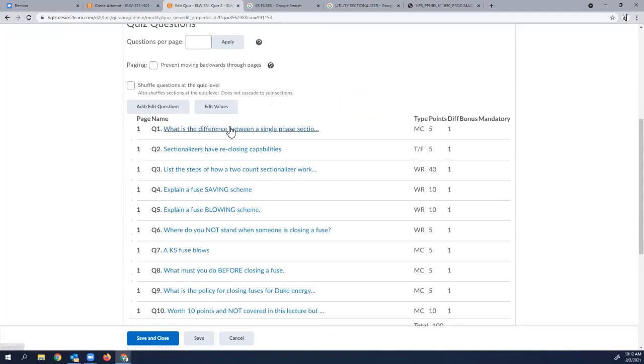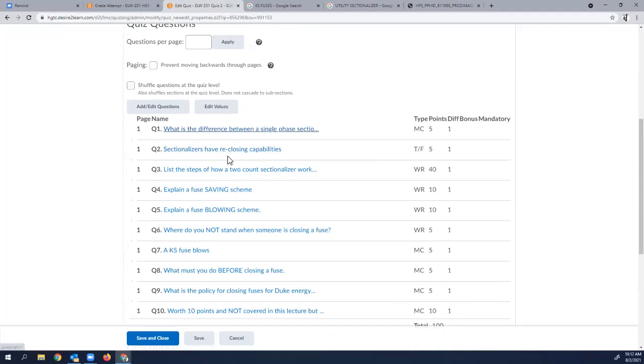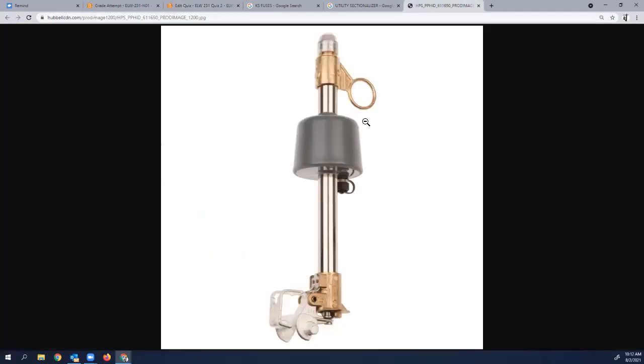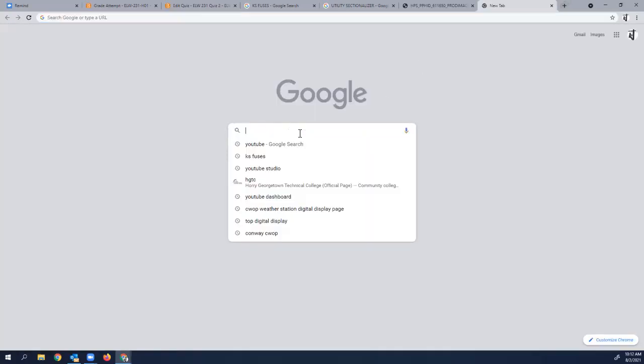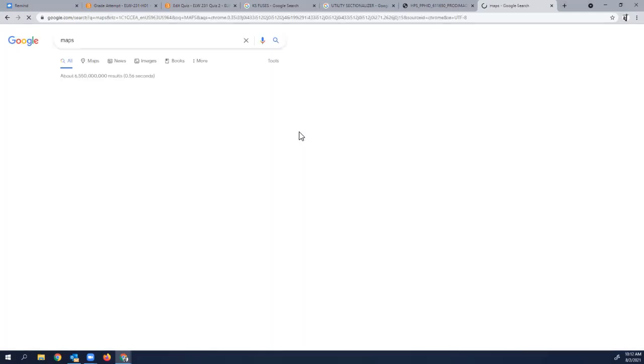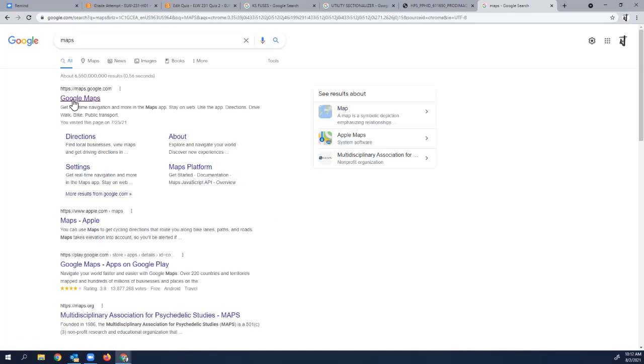Quiz question: What's the difference between a single-phase and a three-phase sectionalizer? That's multiple choice. Sectionalizers do not have reclosing capabilities — they open and stay open. These sectionalizers carry up to 300 amps, giving more capability than a fuse.